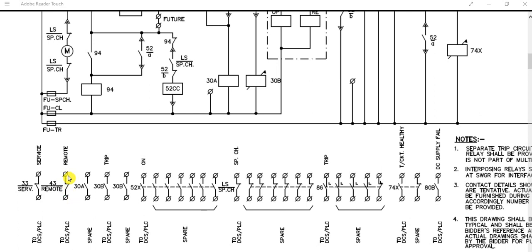Only when the remote position is selected can you issue a trip or close command to the switchgear to close or trip the circuit breaker. So it is very important to select the control switch position to remote — this is the feedback to DCS or PLC.